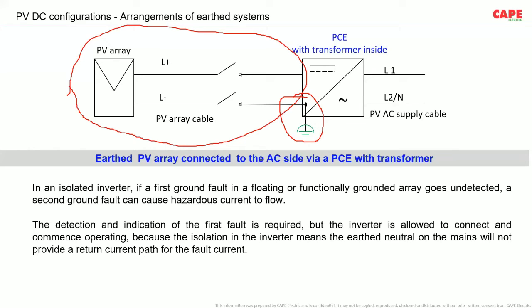If the inverter manufacturer is not taking care of it, he must write it in his manual. And if he has written it in his manual, then it is the job of the installer to take appropriate measures. Now, whether the PCE manufacturer makes this facility inside the inverter is a big question, because nowadays for solar PV, day by day we try to reduce the cost. You have to be sure that if you try to reduce the cost of the inverter or the PCE, then of course such safety measures will also be extra. They will simply remove it and put it in the manual. So the installer has to read it, understand it, and put it in the system.